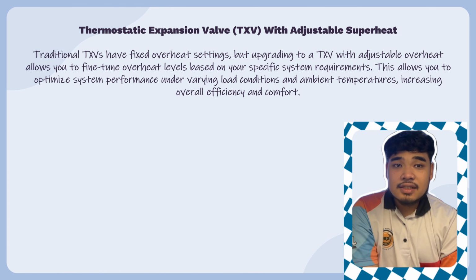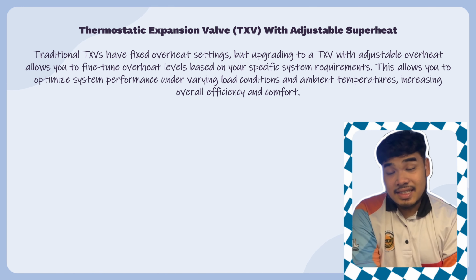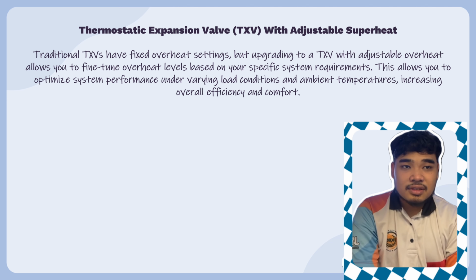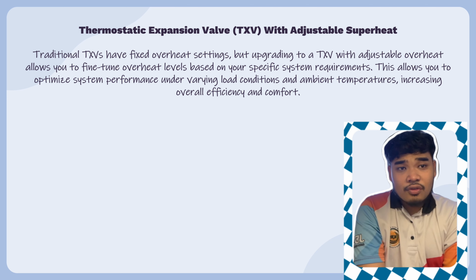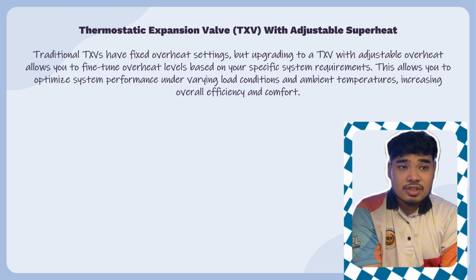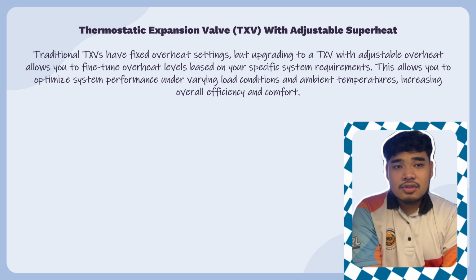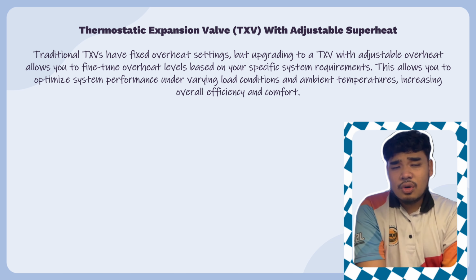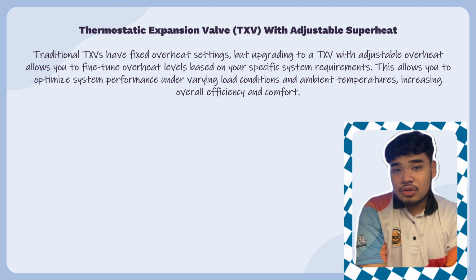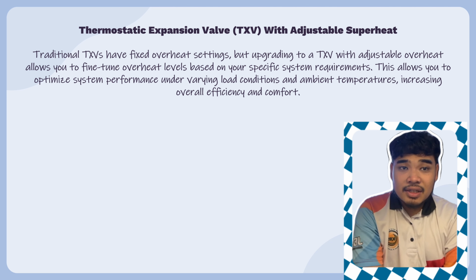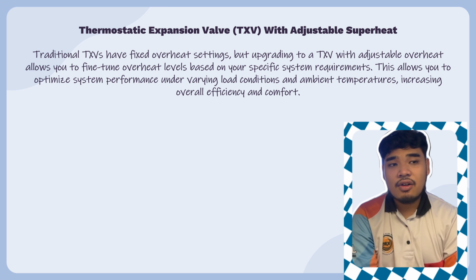So the second one is thermostatic expansion valve, which is TXV, with adjustable superheat, that allows you to fine tune the superheat level based on your specific system requirement. So this also allows you to optimize system performance under varying load condition and ambient temperature, increasing overall efficiency and comfort.